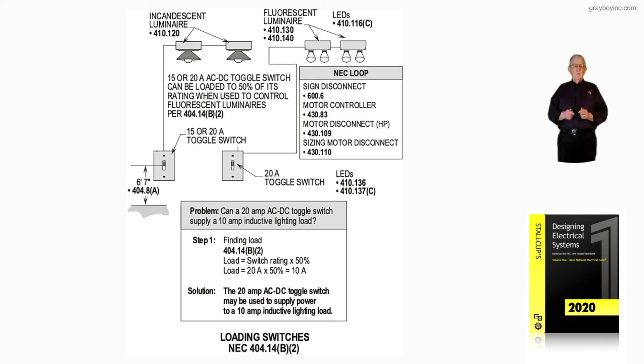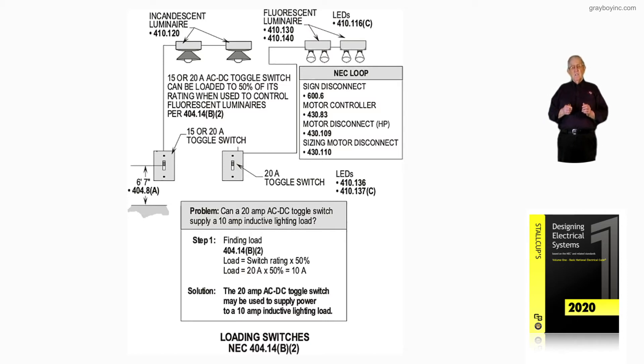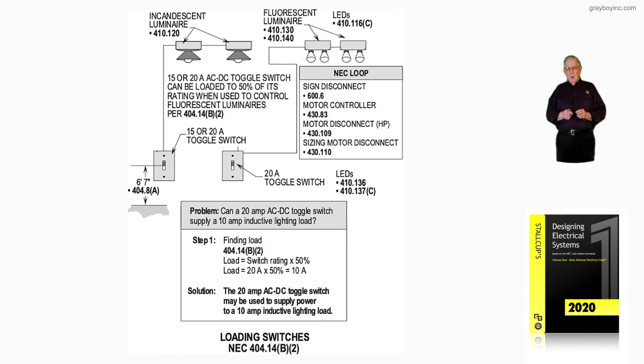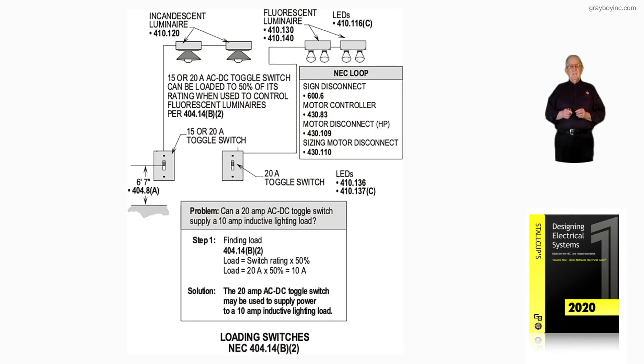Here we're dealing with an AC-DC switch. We pointed out earlier in the presentation that an AC switch can be loaded up to 100% with inductive loading. But if we have inductive loading with a DC switch or AC-DC rated switch, that's 50% loading.